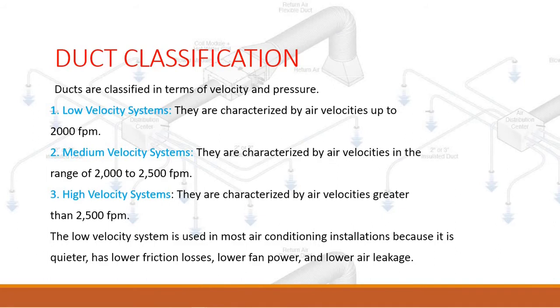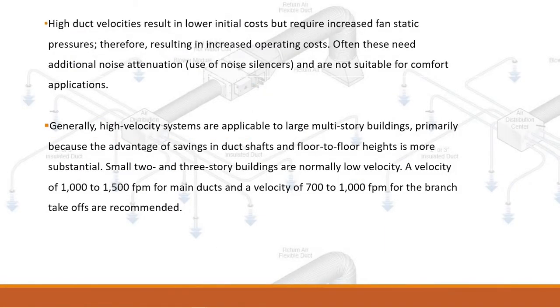The low velocity system is used in most air conditioning installations because it is quieter, has lower friction losses, lower fan power, and lower air leakage. High duct velocities result in lower initial costs but require increased fan static pressures, therefore resulting in increased operating costs.